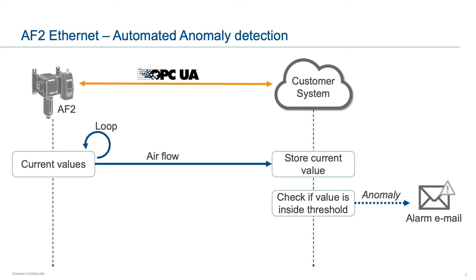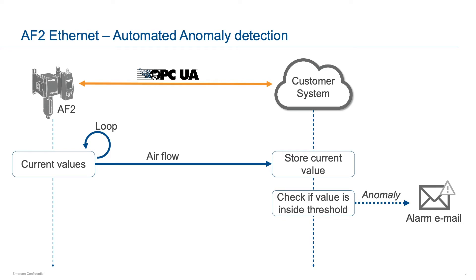we can see how by using an OPC UA connection, we can collect the current airflow values on a periodic basis and then compare them against previously stored nominals for the equipment as it passes through the different cycles. When passing a predetermined threshold, a call to action can be made to the operation staff in the form of an alert such as an email to fix a potential pending problem.